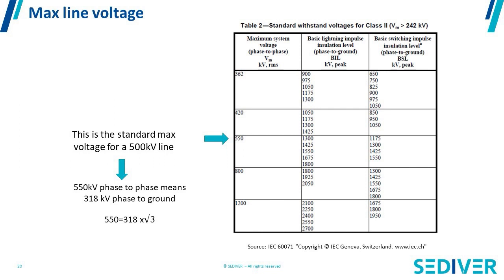The switching is always lower than the lightning impulse. When we talk about a 500 kV line — which is in fact a 550 kV line — we are talking about the phase-to-phase voltage between two conductors. On an AC line with three conductors, you have 550 kV between two conductors. But if you divide 550 kV by the square root of three, you get 318 kV, which is the phase-to-ground value. So between phases you have 500 kV, but between conductor and ground you have approximately 300 kV. The insulator string insulates the phase-to-ground value, not phase-to-phase.